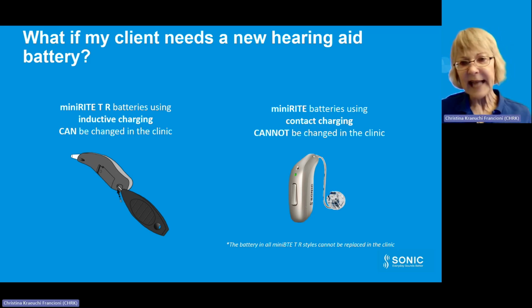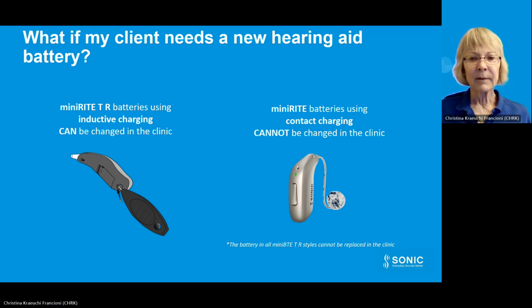Replacing the battery depends on the style and type of charging the hearing aids use. For clients with inductive charging mini-RITE TR hearing aids, the battery can be replaced in the clinic by the clinician. A lithium-ion battery can be lethal if it's swallowed by humans or animals, which is the reason the hearing aids must have a tamper-resistant battery drawer, and the battery may only be replaced by a professional. The battery cannot be disposed of in the garbage. Very, very important: it must be recycled according to the laws and regulations in your country.